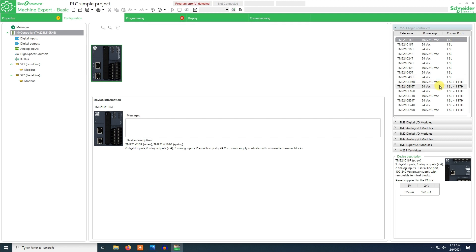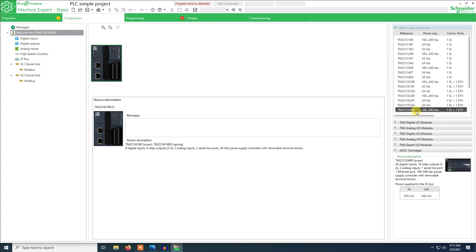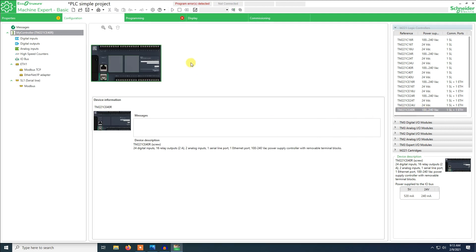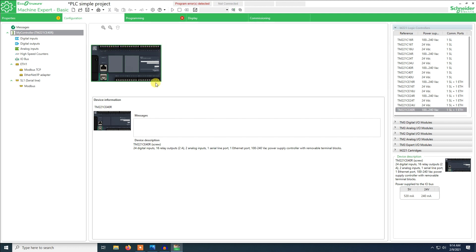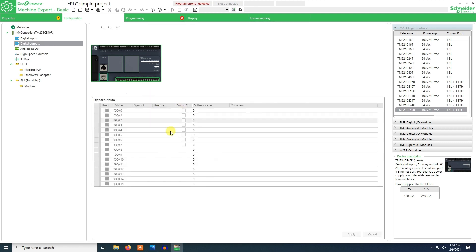Now we go to the configuration. The PLC I'm using — we just drag the PLC in. As you can see, this is the PLC I'm using. Here is a serial port where you can connect RS-485 devices that are RTU, like temperature sensors and level sensors. Here you have the network connection, the TCP, where you can set the IP so that you can have Modbus communication over IP. These are the inputs — we have 24 inputs — and these are the outputs; you have 16 outputs.